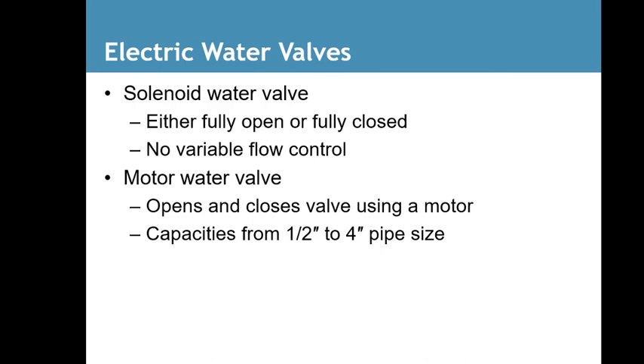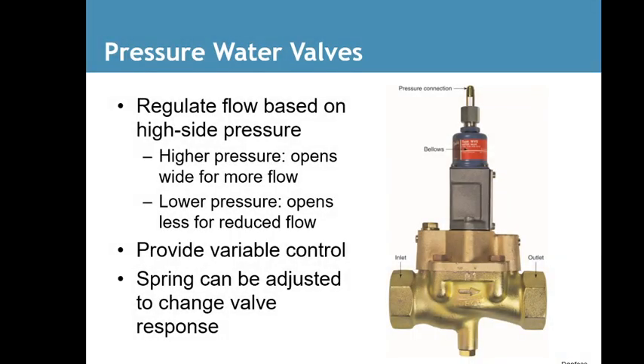Electric water valves: solenoid water valves are either fully open or fully closed. No variable flow control on a solenoid water valve. Motor water valve opens and closes the valve using a motor, capacities from 1/2 inch to 4-inch pipes. Pressure water valves regulate flow based on high side pressures. Higher side pressures open wider for more flow. Lower pressure opens less for reduced flow. Provides variable control. Springs can be adjusted to change valve response.